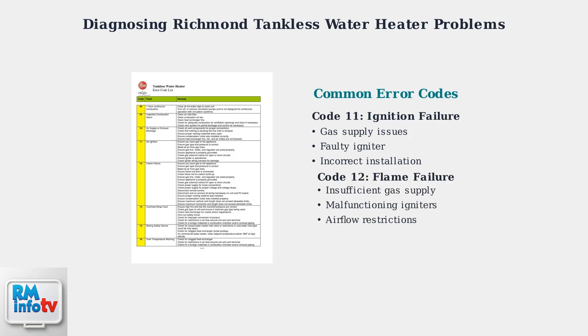Code 12 represents flame failure, meaning the heater attempts to ignite but cannot sustain a flame. This is typically due to insufficient gas supply, malfunctioning igniters, or airflow restrictions.